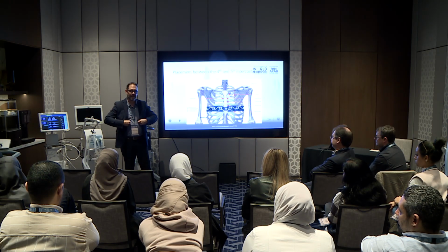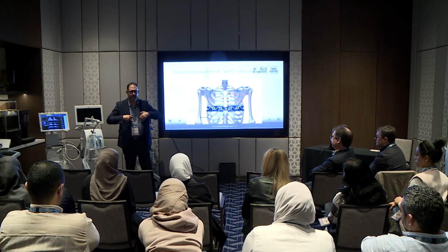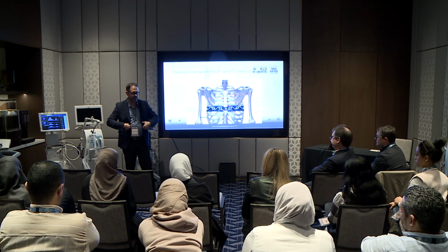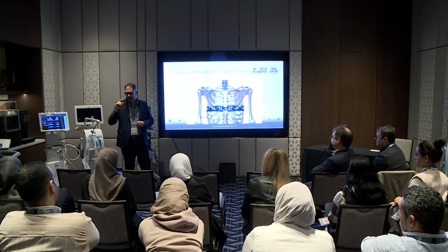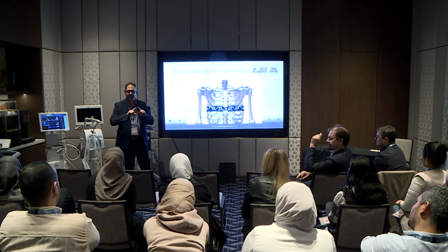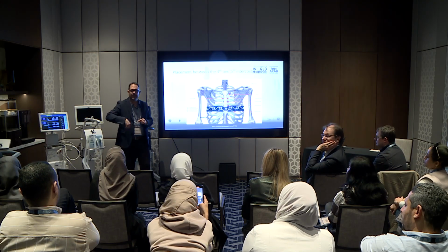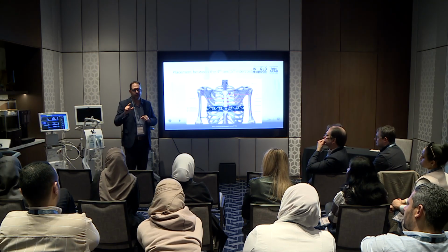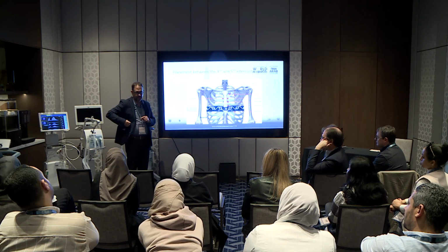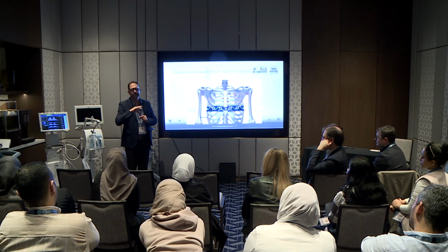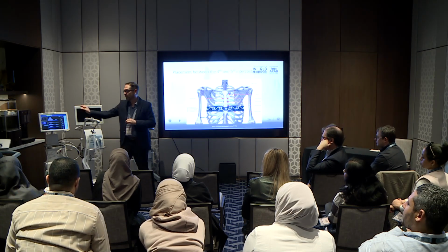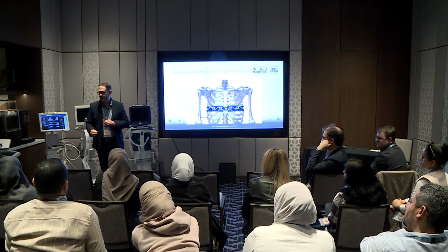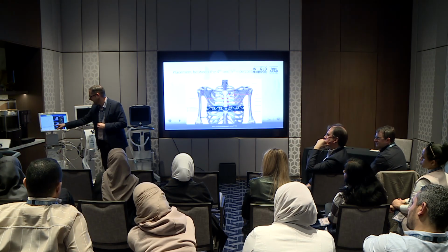If you have any bandages or something you need to avoid, it's better to go up than it is to go down if you have to move the device. The device will function; this one has 16 leads. If you have a chest tube, for example, it could work if it's missing one lead, but if you have 2 leads missing, it starts to have an issue, and it will usually warn you saying the signal quality is low, and there's ways of checking the signal accuracy.